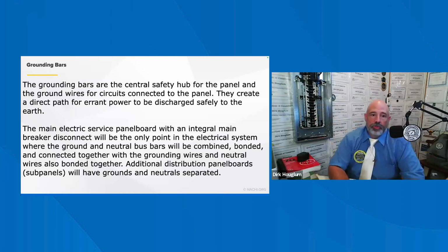The main electrical service panel board with the integrated main circuit breaker disconnect will be the only point in the electrical system where the ground and neutral bus bar is combined. I keep saying that over and over again. I want you to make sure that you get that in your head.